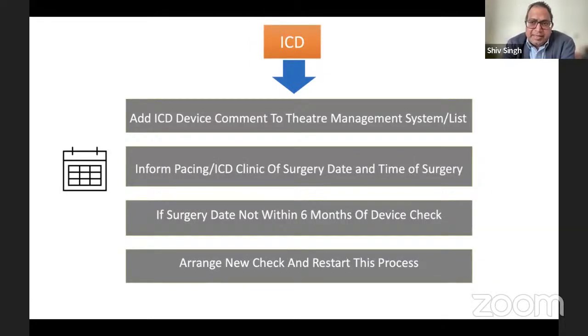Now, if this is an ICD, then it becomes a little bit more complex, because the theater list should include this information. The anesthetists involved need to be told that a patient with an ICD is coming onto the list. You need to inform the physiology lab, the cardiorespiratory lab, where the check will be done. And you need to make sure that the device has been checked within the last 6 months. And if it is not, then you arrange for these checks.